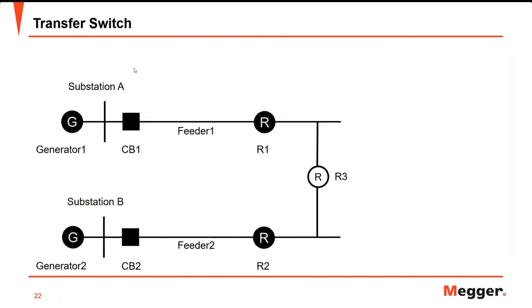Transfer switch: if a fault occurs in a portion of feeder one, circuit breaker one will trip and the whole feeder one will be de-energized. Recloser one will open in preparation for load shifting, and recloser three will be closed, energizing the end portion of feeder one. This can be done manually or automatically in a smart or self-healing grid.